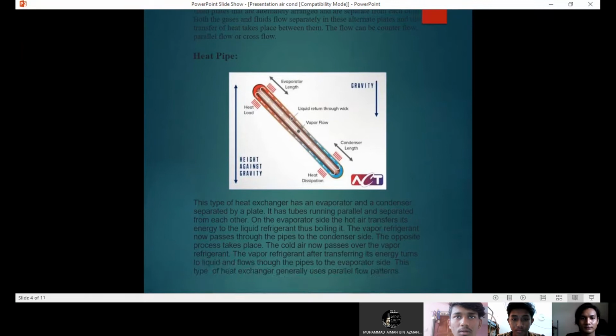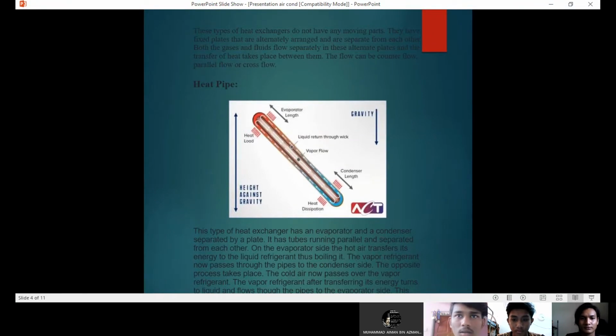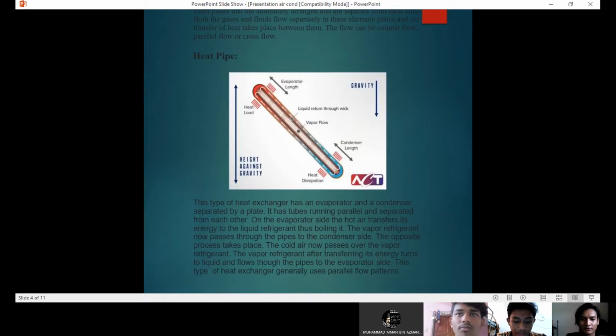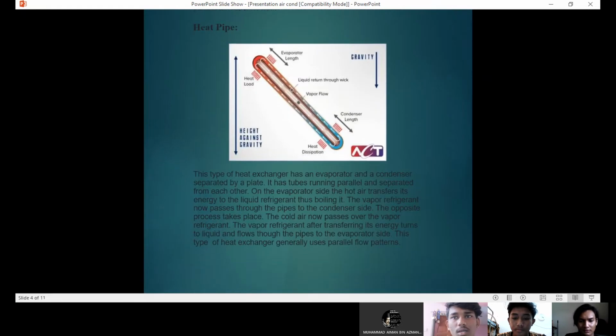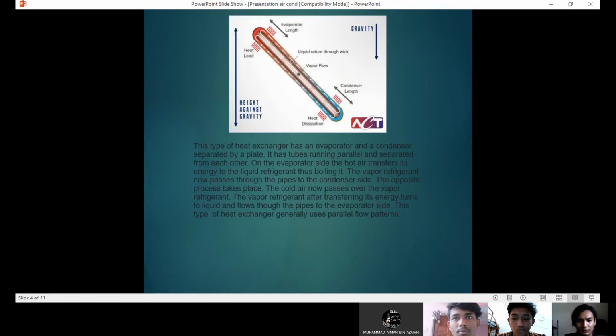And the following heat exchanger is the heat pipe. This type of heat exchanger has an evaporator and a condenser separated by a plate. It has tubes running parallel and separated from each other. On the evaporator side, the hot air transfers its energy to the liquid refrigerant, thus boiling it. The vapor refrigerant now passes through the pipes to the condenser side. The opposite process takes place. The cooler air now passes over the vapor refrigerant. The vapor refrigerant, after transferring its energy, turns to liquid and flows through the pipes to the evaporator side. This type of exchanger generally uses parallel flow patterns. That's all.